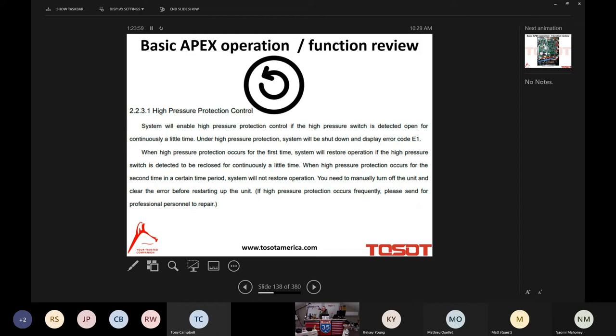But before it does that, all Tosot systems, whether they be Apex or mini split units, guys, one of the extraordinary features of the Tosot systems is that they try to solve problems before letting you know about them. And this is the perfect example of that. If the system's experiencing high pressure, the system literally has the capability of controlling the operation, controlling the modulation, controlling the RPM of the compressor. You now know how an inverter compressor works. If the pressure is too high, we could slow it down, baby. And if it's too low, we can do the opposite and speed it up.